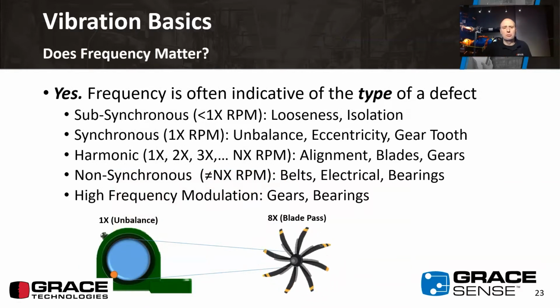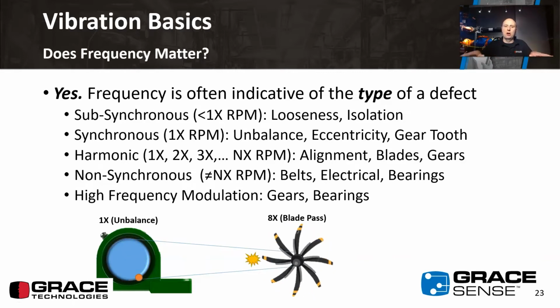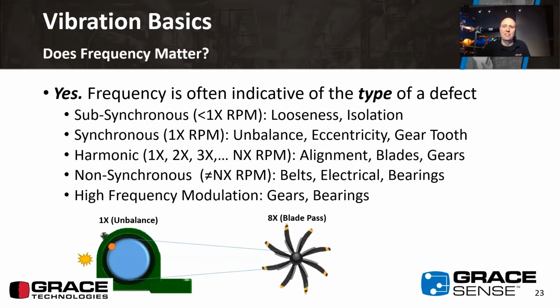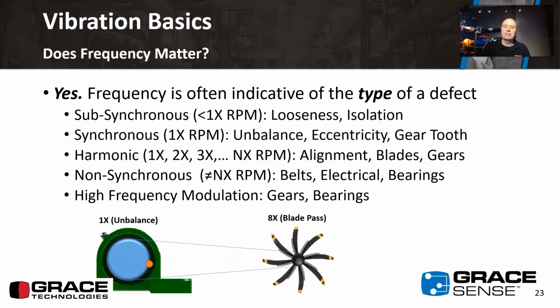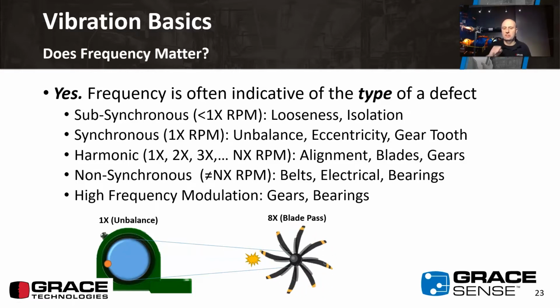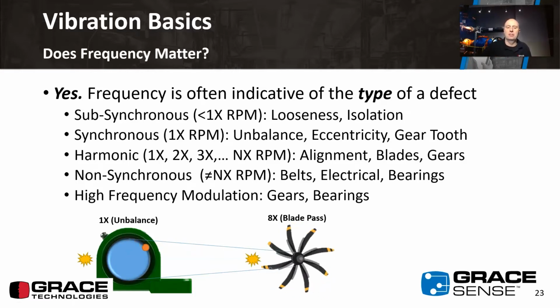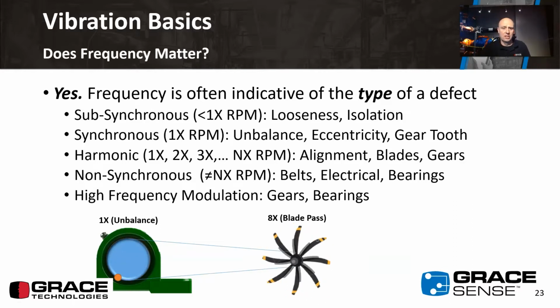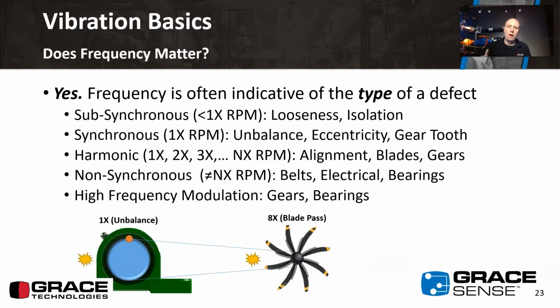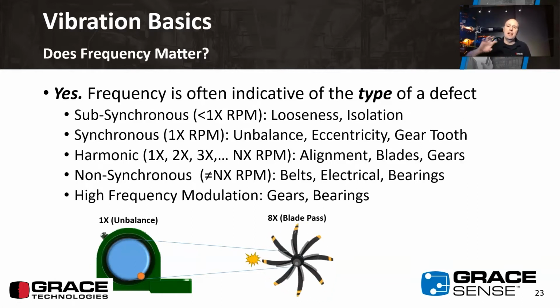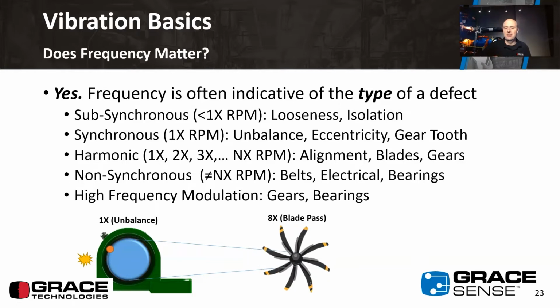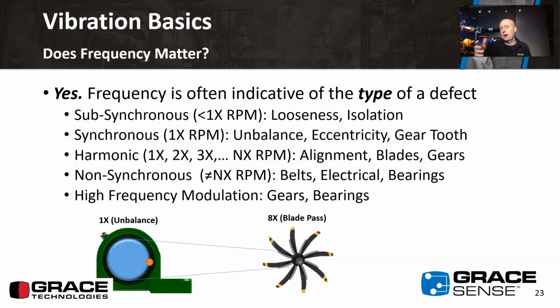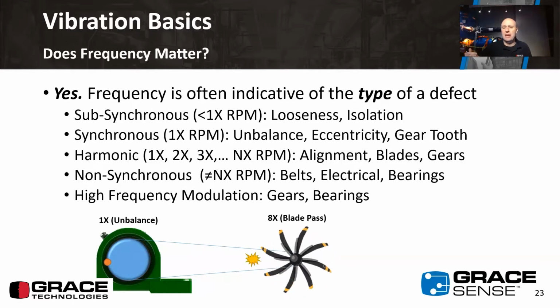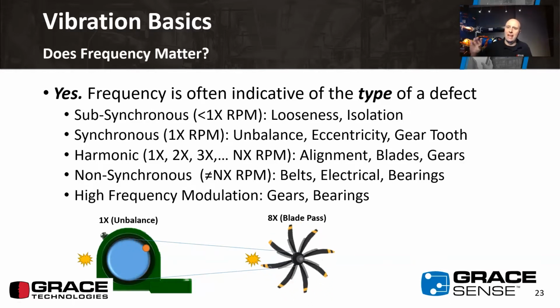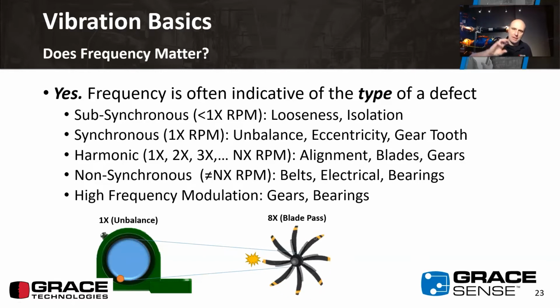So we've talked a little bit about frequency from the perspective of this mattering depending on how you're monitoring, but it also allows us to indicate the type of defect we're looking at. This graphic gives a simple example of how this might play out. If we have an unbalance taking place, we're going to see that unbalance at 1 times the shaft speed—every time that shaft rotates, we experience 1 cycle of that defect. Whereas if we had some issue with one of these fan blades, we're actually going to see that turn 8 times every time that shaft spins.